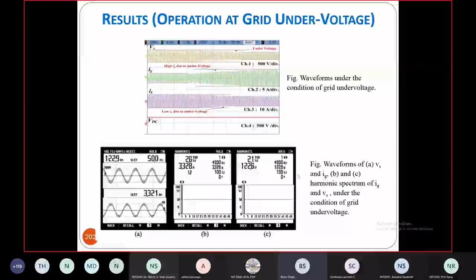But the THD you can see is around 2.6% for the grid current also. And even if the voltage is distorted - in the case where we modify the control such that voltage is quite distorted at 7.8% THD - current THD is still maintained at 2.1%, much lesser.